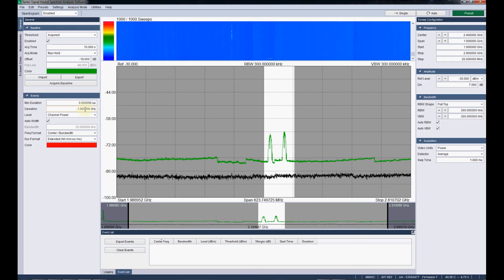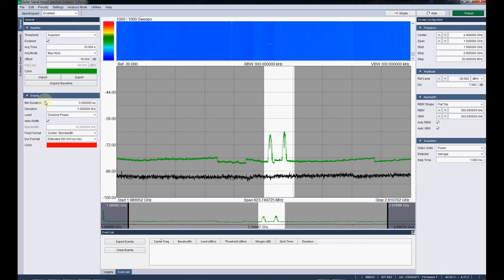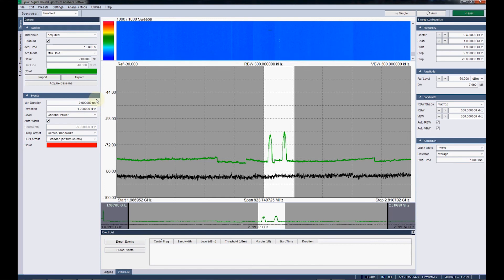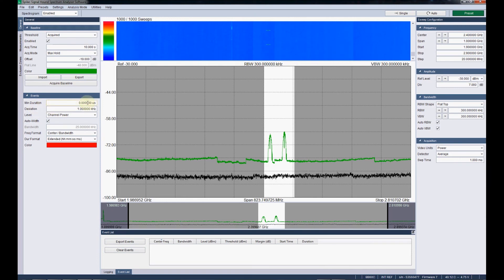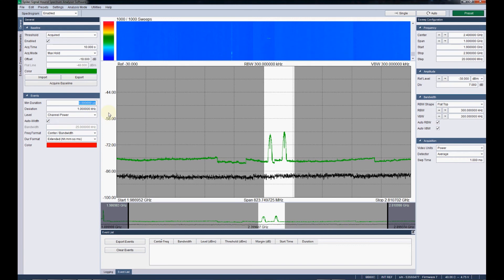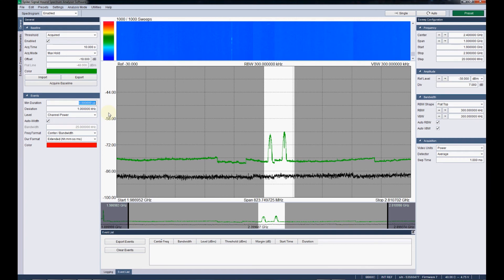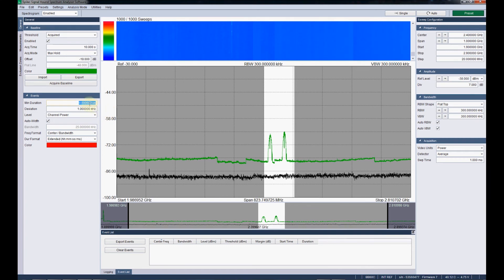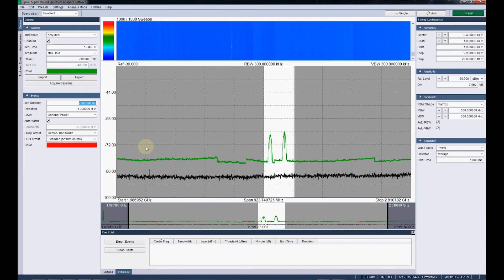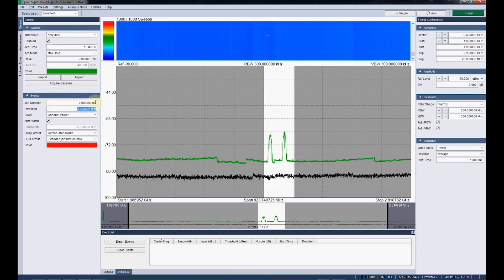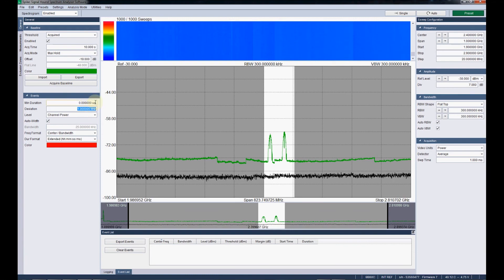One thing that I will mention that I didn't discuss before. You may not need to mess with too much, but for events, once you have a baseline and are capturing events, this minimum duration and frequency deviation fields, the minimum duration specifies the minimum, I mean, it's self-explanatory, but the minimum amount of time that an event has to persist for you to consider it an event. So if you had really steady signals, you might crank this up a little bit in order to not worry about blips, if you didn't want to worry about really brief signals. On the other hand, if you want to capture everything, then you would want to keep it at zero, which is the default to make sure, assume that you don't want to miss anything.